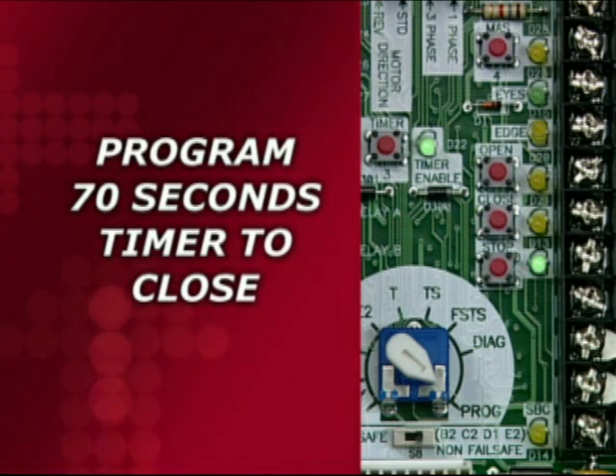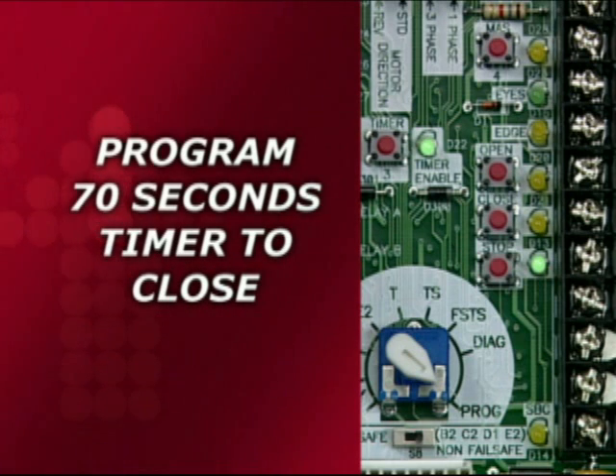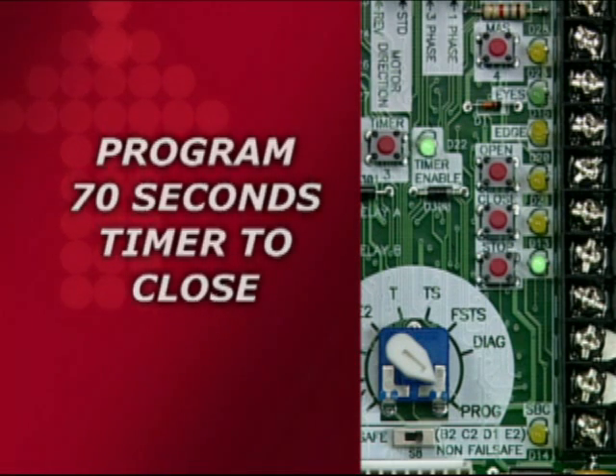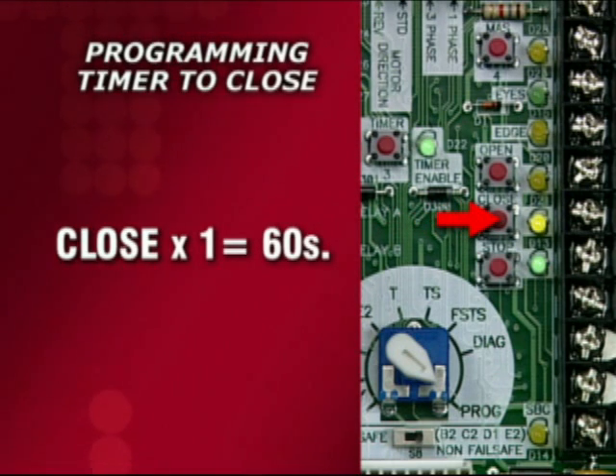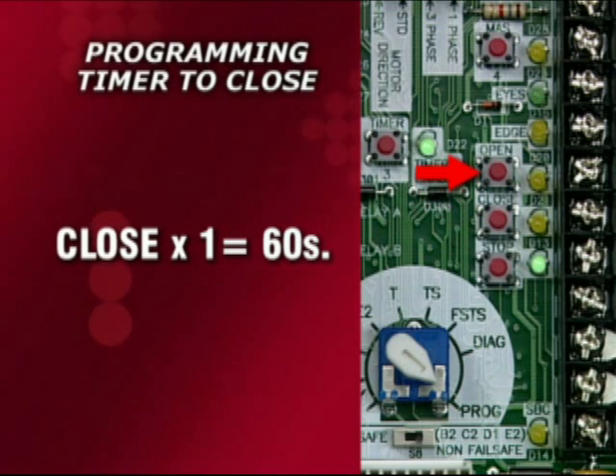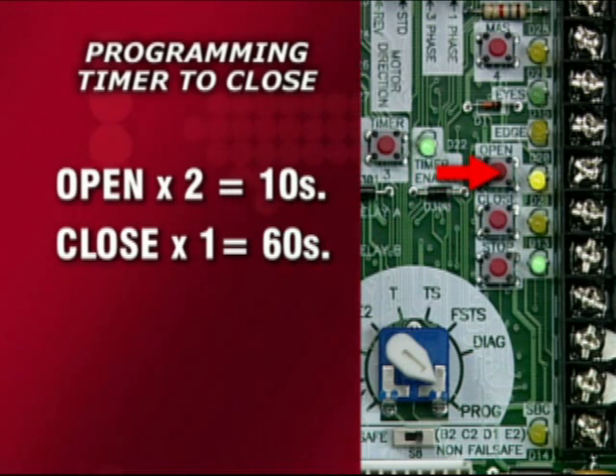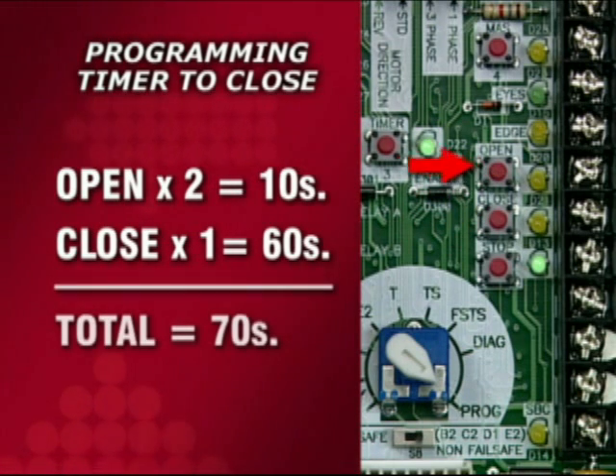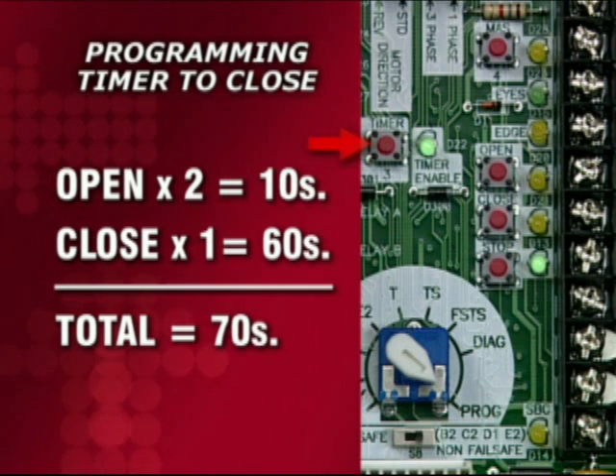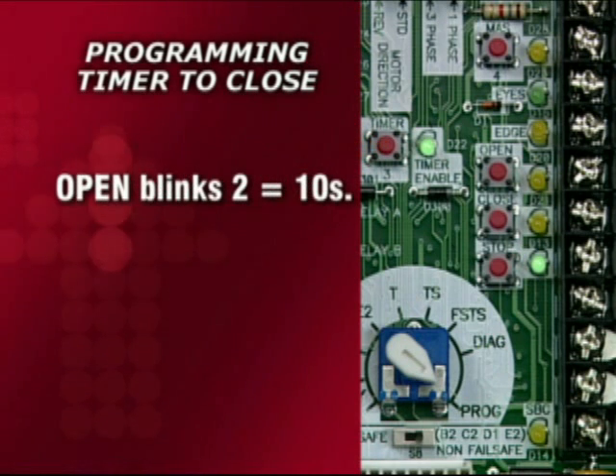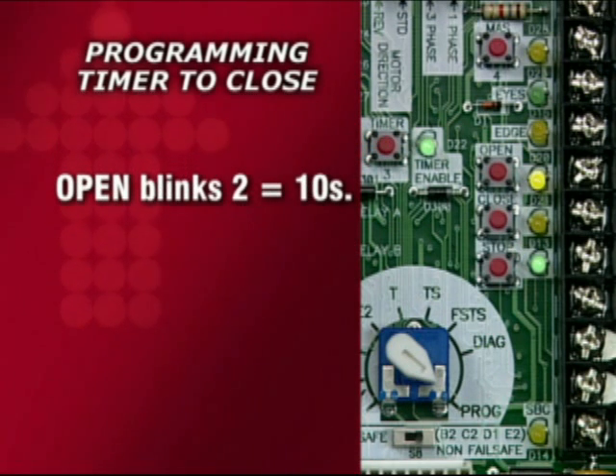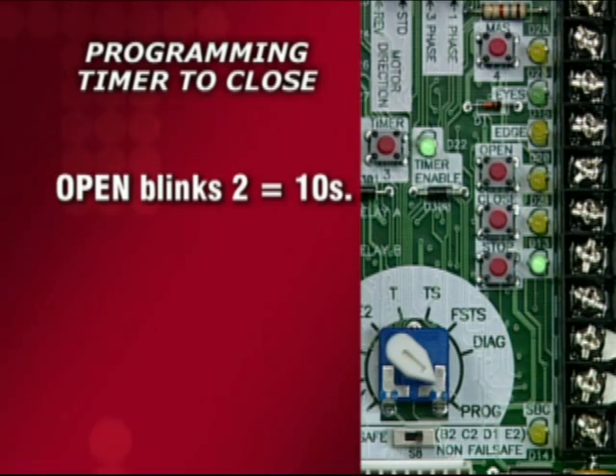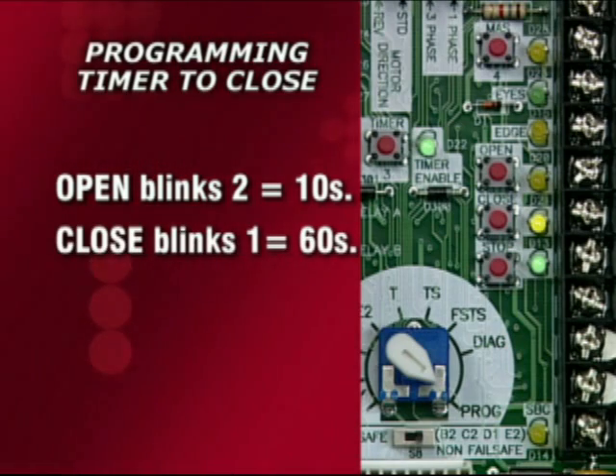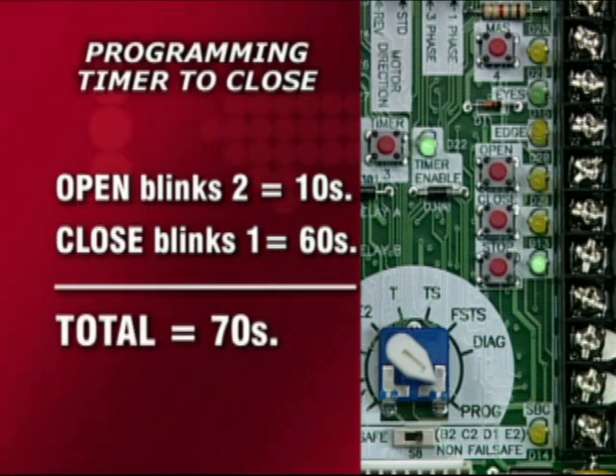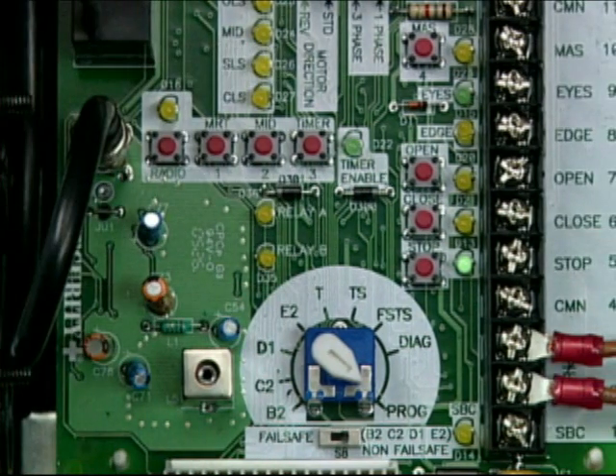Let's look at an example. We will program the timer to close for 70 seconds. Begin by pushing the close button once for 60 seconds. Then push the open button twice for 10 seconds. Press the timer button on the logic board to complete programming. The open LED will blink once for every 5 seconds programmed. The close LED will blink once for every 60 seconds programmed. To finish programming, turn the selector dial back to the desired wiring type.